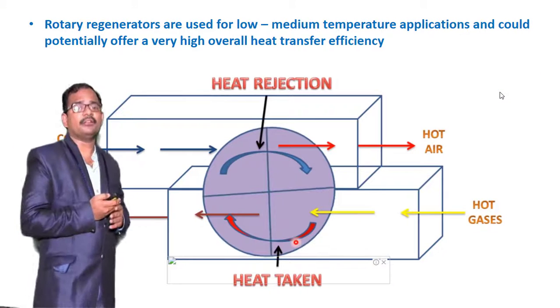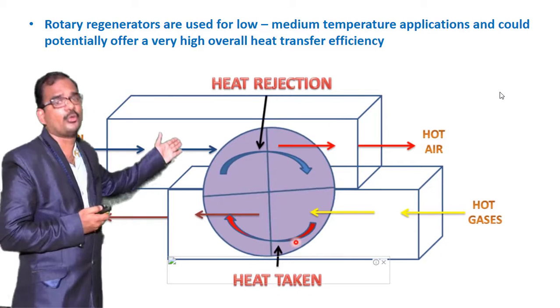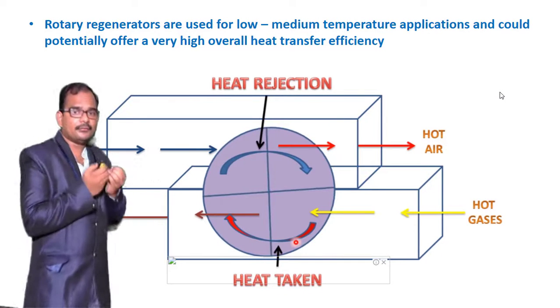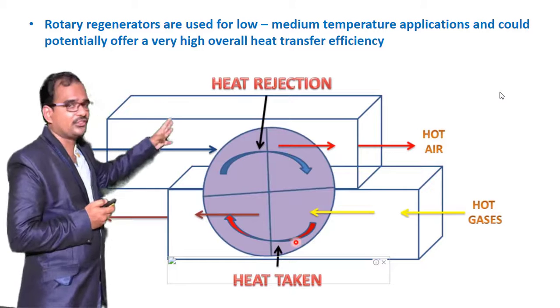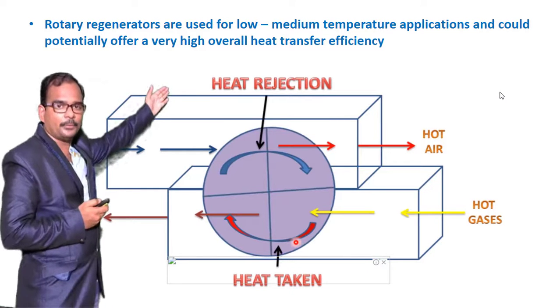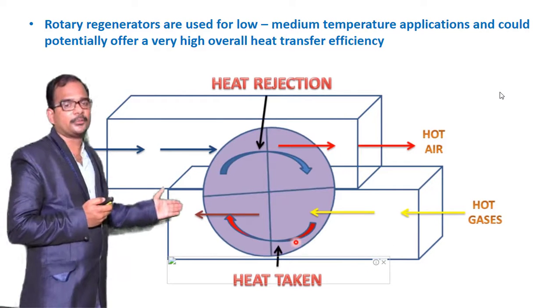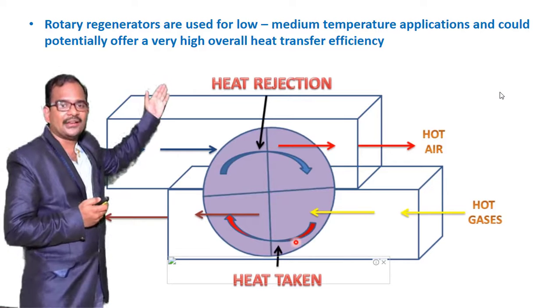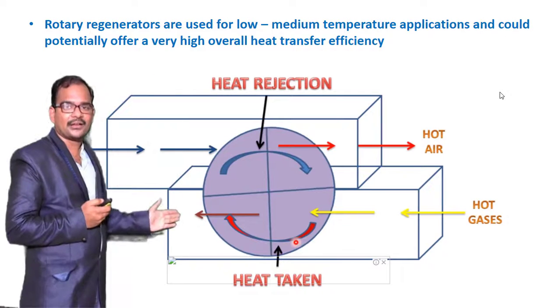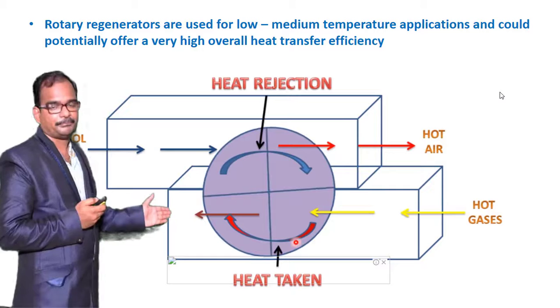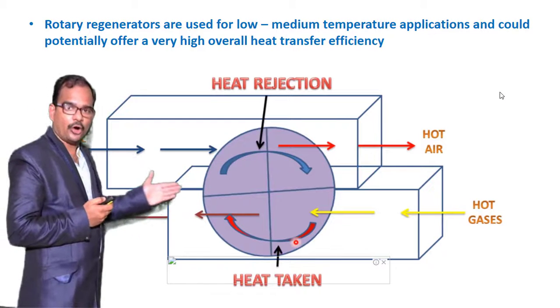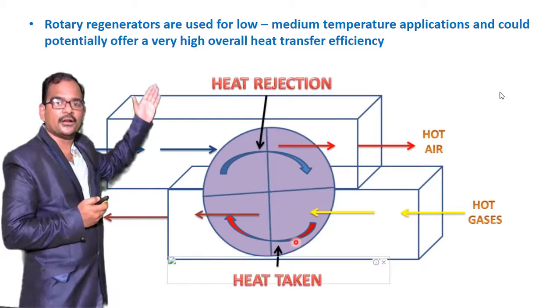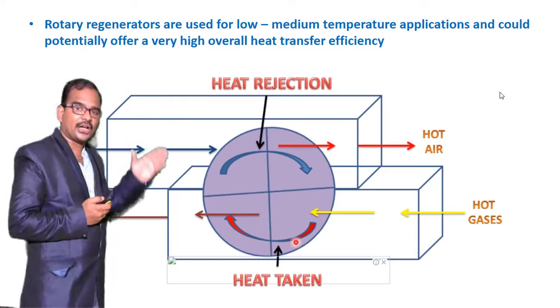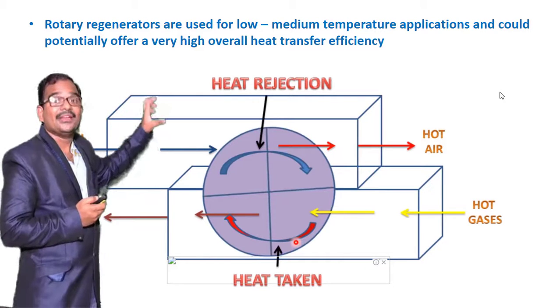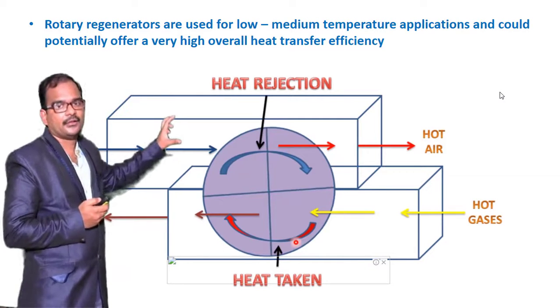So how will this work? You can see the picture here. There are two ducts: the top duct and the bottom duct. The top duct carries cold air and the bottom duct carries flue gases. So the bottom one is the hot duct and the top one is the cold duct. In between these two ducts, you place the heat wheel.